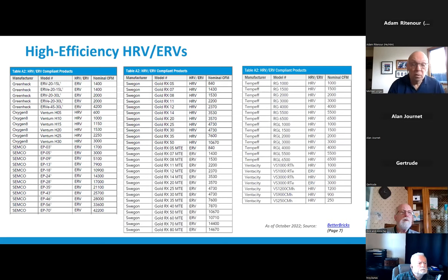These are parts of the table that you can find at betterbricks.com that show the different manufacturers and their models that have gone through third-party testing and that have been proven to be compliant for VHE DOAS. So there are over 70 specific models from 6 manufacturers. And you can see that they range in size from 250 CFM all the way up to over 42,000 CFM. So there really is an HRV or ERV size for any building.